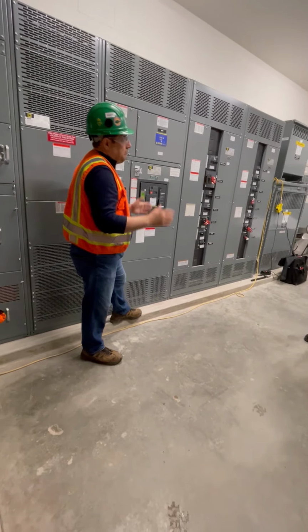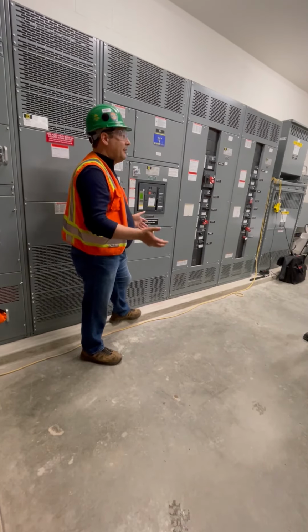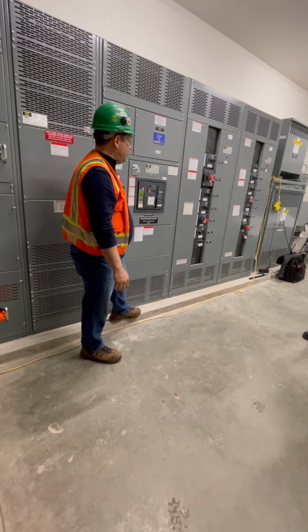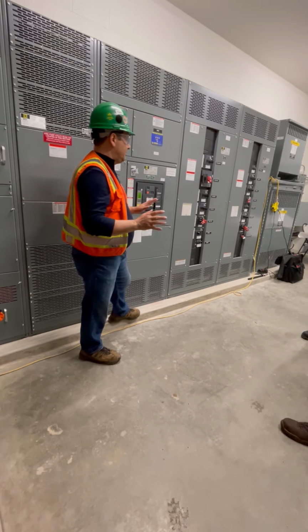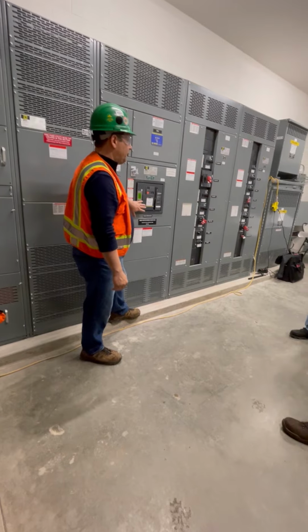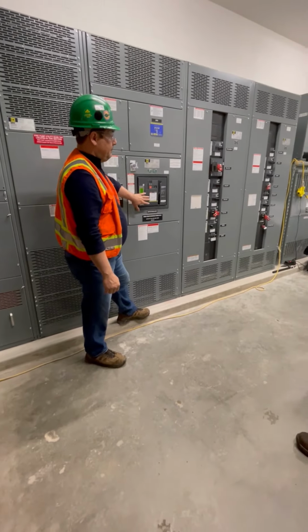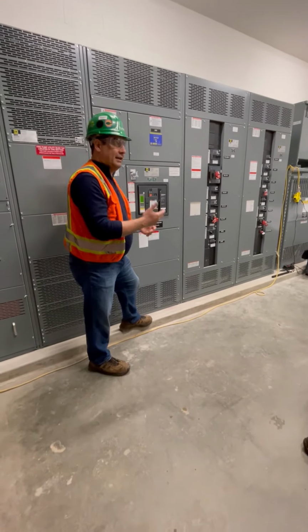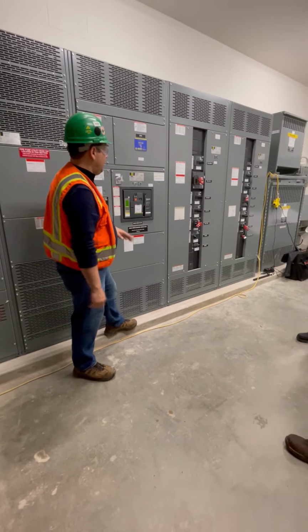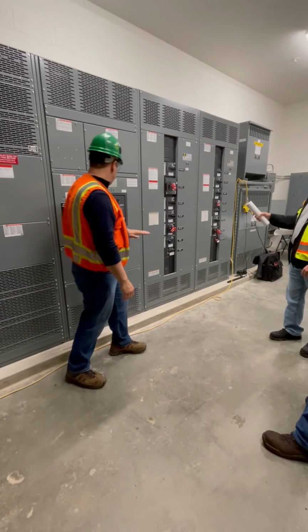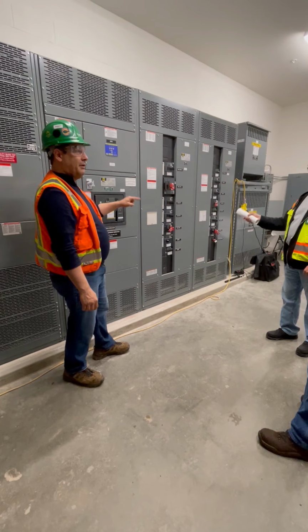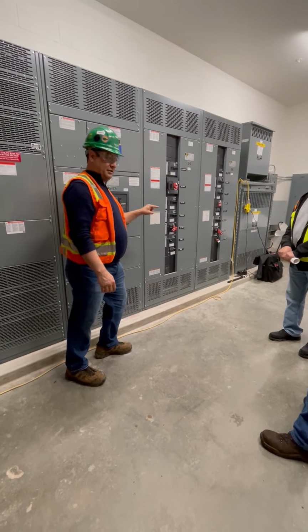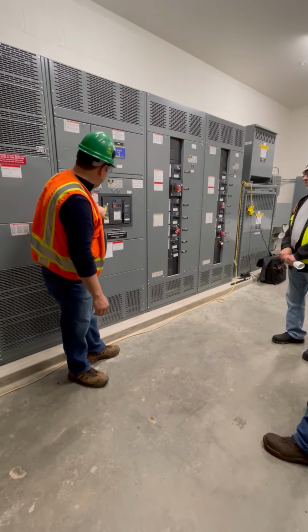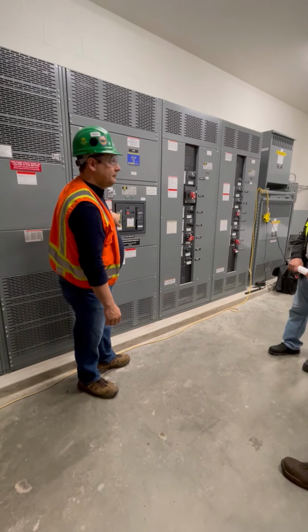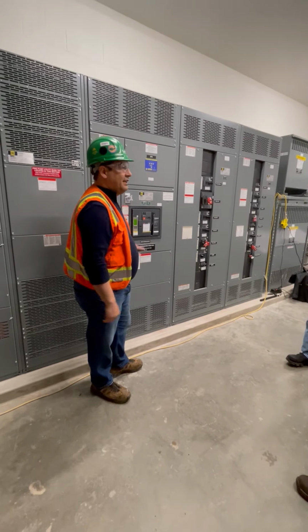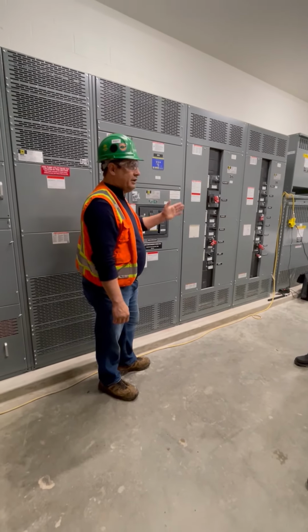Now, kind of a pointer, if that happens, what I tell customers to do is, because trust me, I've been through it, the customer is under stress to get the building back online and they don't know what tripped it. You turn all these feeders off, turn this one on, start one by one. Process of elimination, right? Yep. So if the LED comes on ground fault, that's something you may want to think about, and then try to figure out where the feeder is.